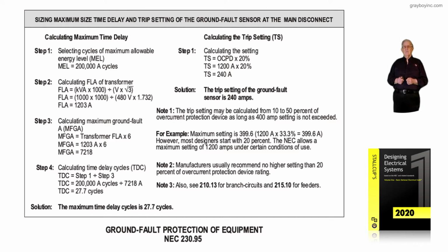Now, step 1 in the illustration is the trip setting, so important. If you should have 1,200 amps and somebody out on the job gets to messing with it and it's tripping and they just put it all in, that is not providing the appropriate setting in many cases. So it's recommended that 20% would be your max, so you'd set it at 240. And if that trip setting did not work, then there's usually something else wrong. So note 1, contact your manufacturer and they will give you the maximum setting that could be used. Now notice in note 1, the trip setting may be calculated from 10 to 50% of the overcurrent device as long as a 400 amp setting is not exceeded. But again, today the manufacturer is going to tell you that, so keep that in mind.